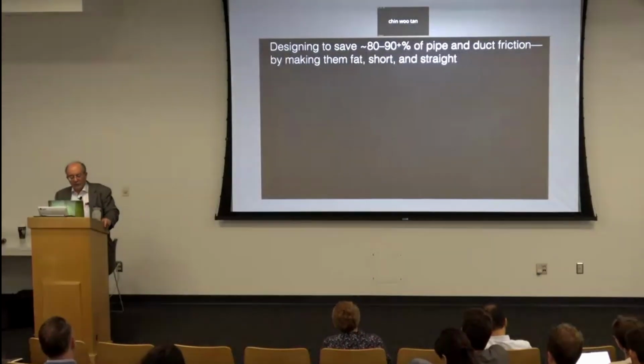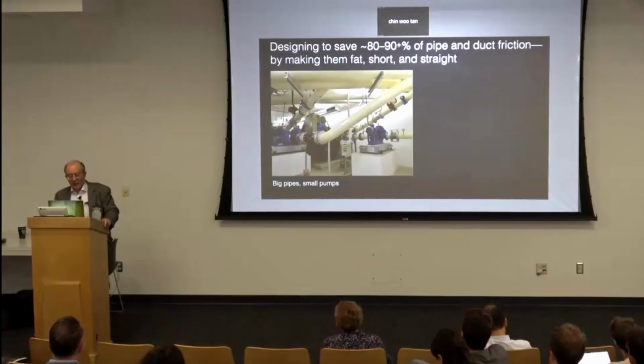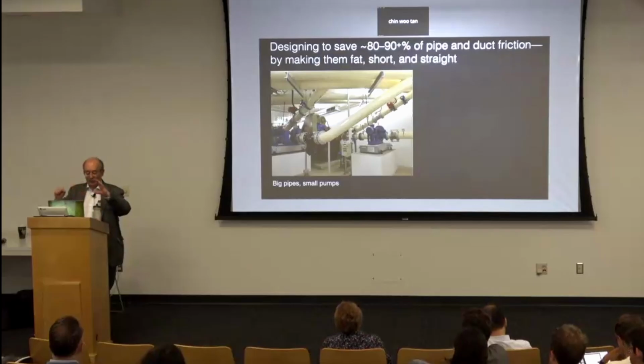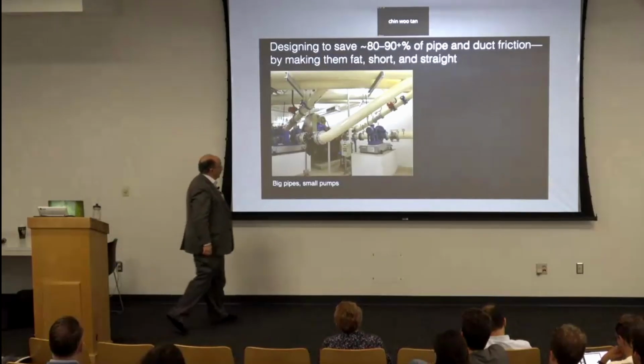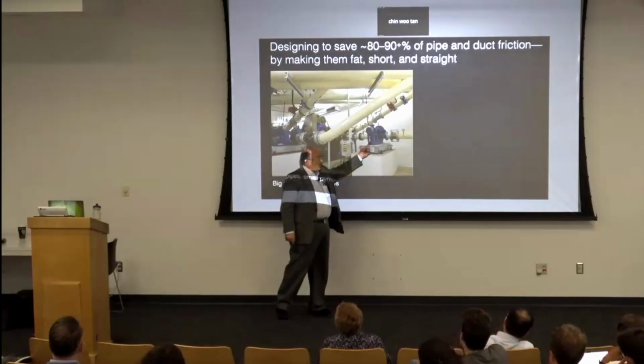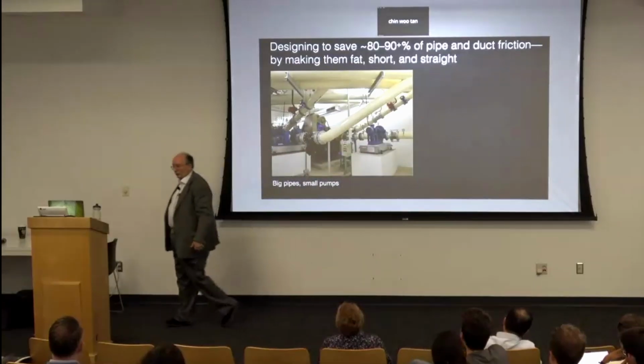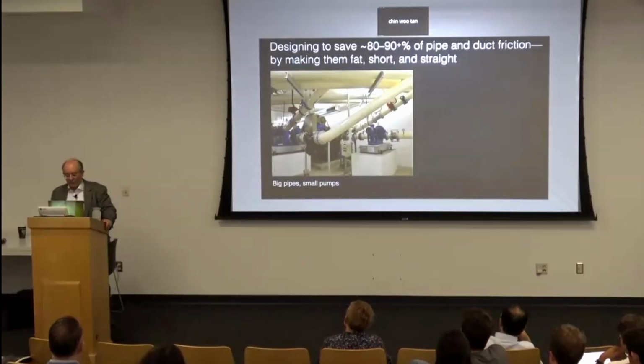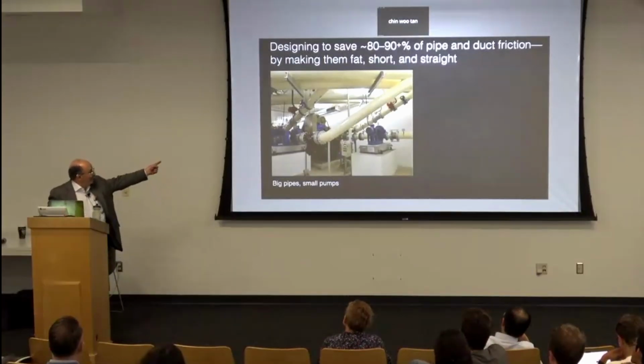In pipes, friction drops as nearly the fifth power of diameter, but cost rises as only about the second power of diameter. So we should use big pipes and small pumps. Fat, low-friction pipes make this little blue pump so small it looks like somebody made a decimal point error, but with the fat pipes, that's all you need. Notice the pump is raised up to meet the pipe rather than conventionally dipping the pipe down to the floor and back up again with 4 elbows full of friction.